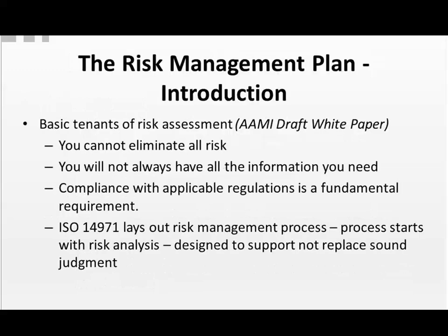Now, before we talk about the risk management plan, though, let's briefly review some basic tenets of risk assessment that apply to the entire process. First, you cannot eliminate all risk. You therefore must determine your risk threshold. That's the level of risk that the organization is willing to accept for your particular device. You'll not always have all the information you need to fully evaluate your risk. Waiting to gather sufficient information can really lead to greater risk. You assess your risk as you go forward, reassessing as you gather more and more information.